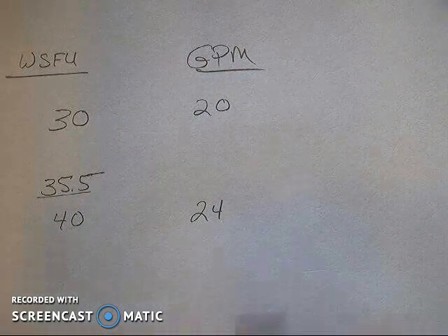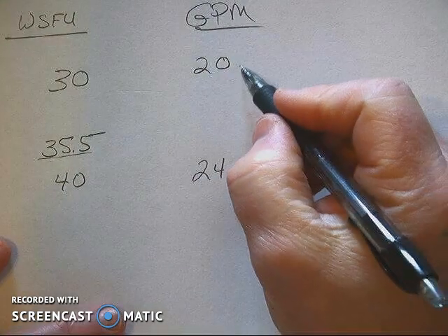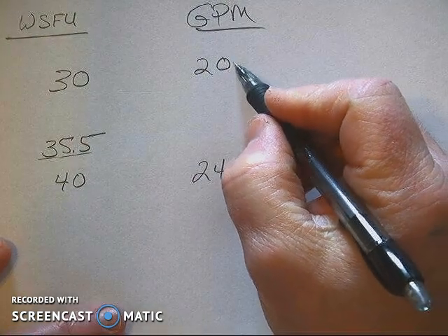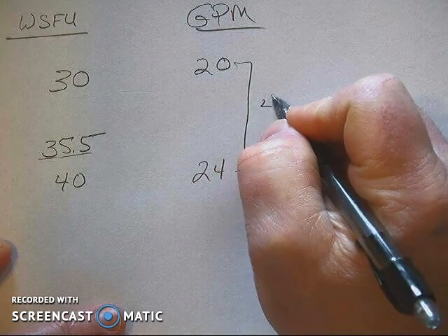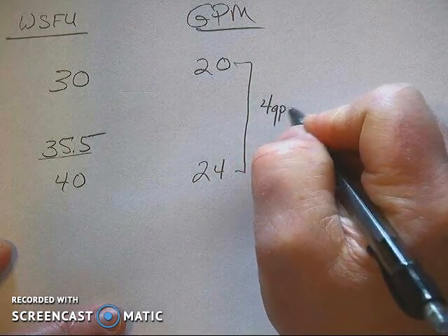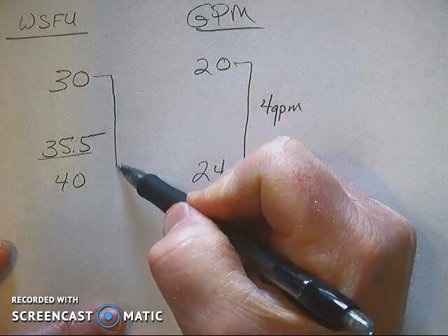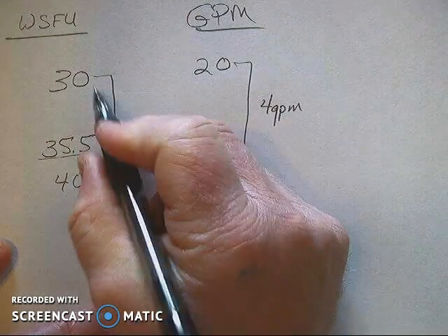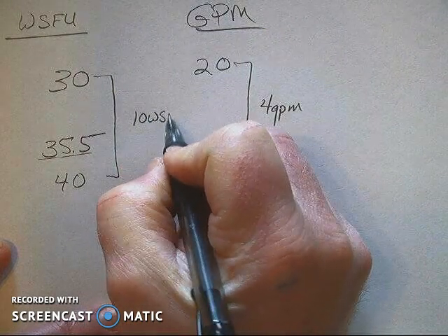Now to start this off, we are going to take a look at the difference in gallons per minute on this side which is 4 GPM, and then we're going to take a look at the difference in WSFU on this side between the two numbers that I do have which is 30 and 40, and the difference between that is 10 WSFU.